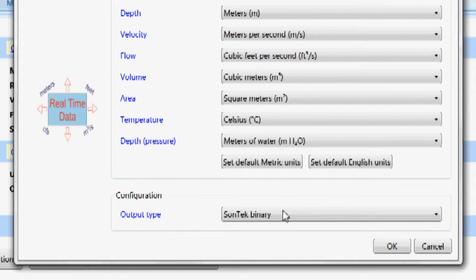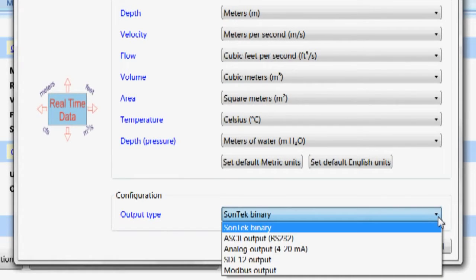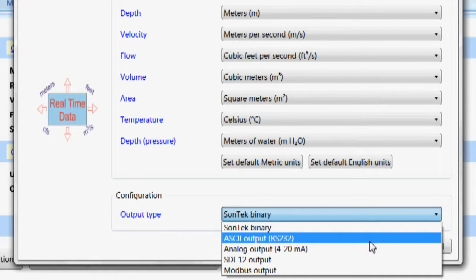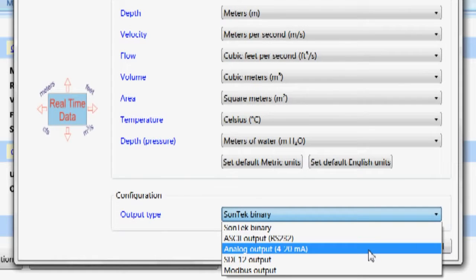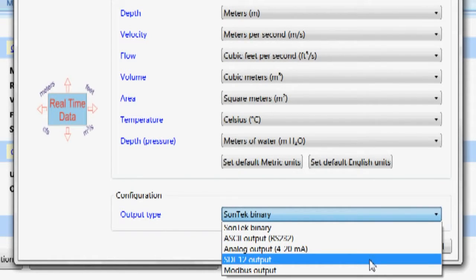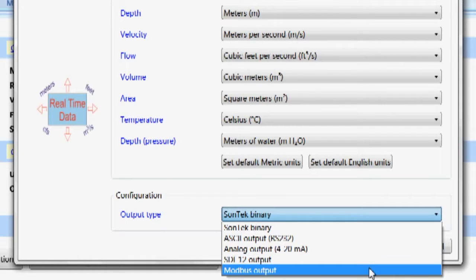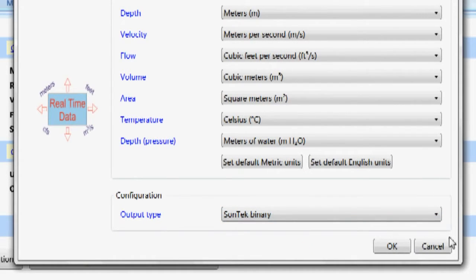The next thing is the output type. These were for units, and this is for the output type. I have a couple options here. I can output it to SonTek binary, meaning I'll just be storing data on the IQ and periodically connect a laptop to download it. If I want to use it for polled mode or connect to an RS-232 device, I can set it for ASCII output. I can also set it to a 4 to 20 milliamp output, SDI-12—which is a very common protocol used with a lot of modern data loggers—and of course Modbus. In this case I'm going to leave it set to binary because I'm just going to be talking to the instrument with my laptop.